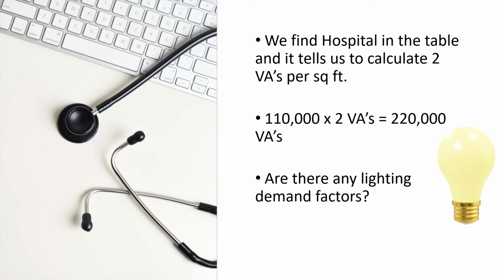Are there any lighting demand factors? Let's check out table 220.42. On the left-hand side, it is going to list the type of occupancy, the lighting VA load is in the middle, and then the demand factor is over to the right. Do you notice hospitals listed in the occupancies? We do, so we can apply these demand factors. It lets us know that the first 50,000 VAs are going to be calculated at 40%, and the remainder over 50,000 are going to be set up at 20%.